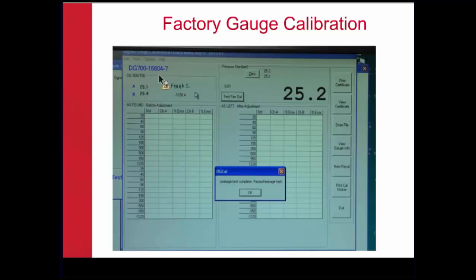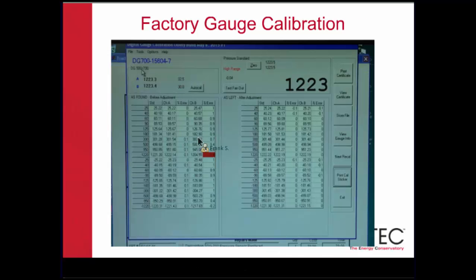Now, let's get back to serial number 15604. We do a leakage test to make sure that all of the hoses are connected and the zero valves are functioning. Then we perform the calibration check. On the left-hand side, you can see this is the as found data, channel A and channel B. You can see channel B now has values because there's a sensor there, and at 1220 pascals positive, we had an error of minus 1.4. This is very characteristic of a brand new sensor being installed into the gauge that has not yet been calibrated. On the right-hand side, you can see this is the as left, or after adjustment. Now channel B shows all of the values at 0 or plus or minus 0.1. For us, this is what we would consider a perfect calibration.